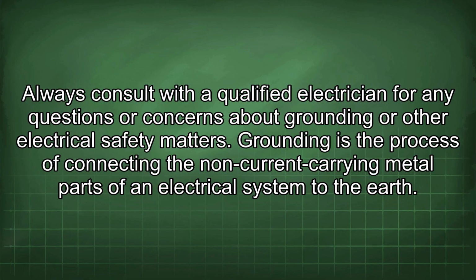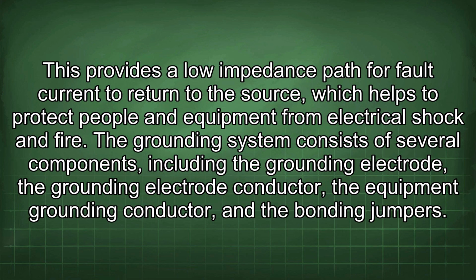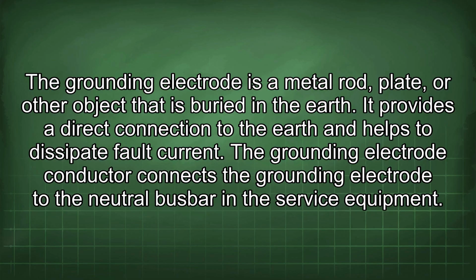Grounding is the process of connecting the non-current carrying metal parts of an electrical system to the earth. This provides a low impedance path for fault current to return to the source, which helps to protect people and equipment from electrical shock and fire. The grounding system consists of several components, including the grounding electrode, the grounding electrode conductor, the equipment grounding conductor, and the bonding jumpers. The grounding electrode is a metal rod, plate, or other object that is buried in the earth.